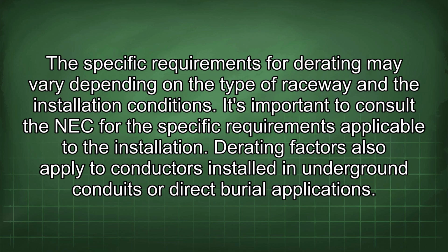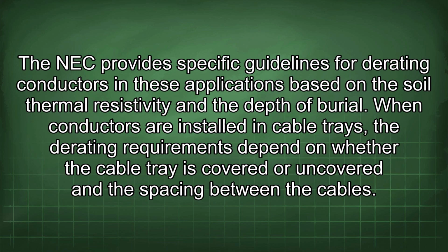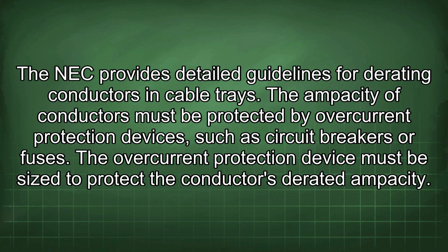Derating factors also apply to conductors installed in underground conduits or direct burial applications. The NEC provides specific guidelines for derating conductors in these applications based on the soil thermal resistivity and the depth of burial. When conductors are installed in cable trays, the derating requirements depend on whether the cable tray is covered or uncovered and the spacing between the cables. The NEC provides detailed guidelines for derating conductors in cable trays.